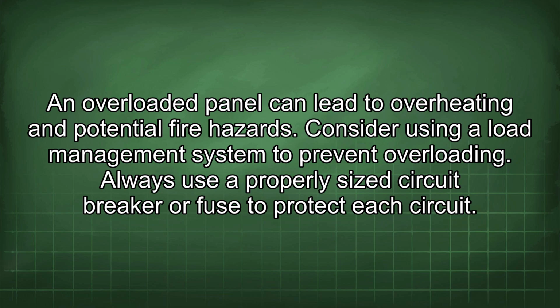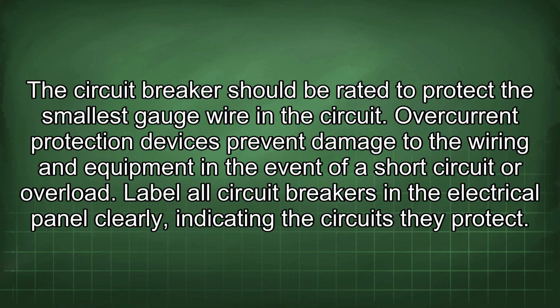Consider using a load management system to prevent overloading. Always use a properly sized circuit breaker or fuse to protect each circuit. The circuit breaker should be rated to protect the smallest gauge wire in the circuit. Overcurrent protection devices prevent damage to the wiring and equipment in the event of a short circuit or overload.